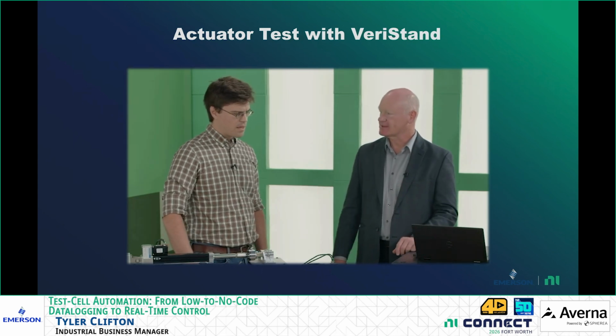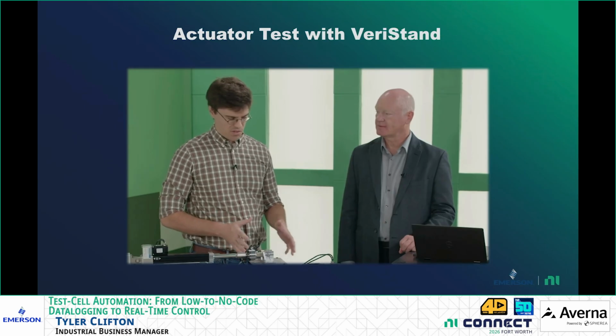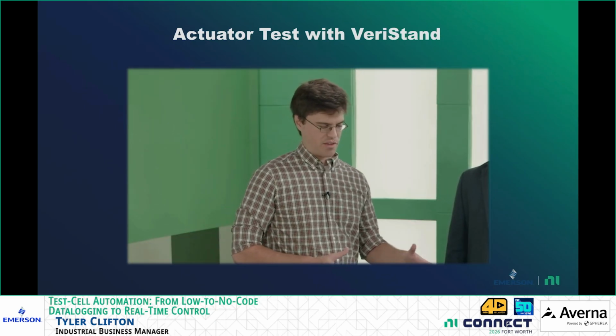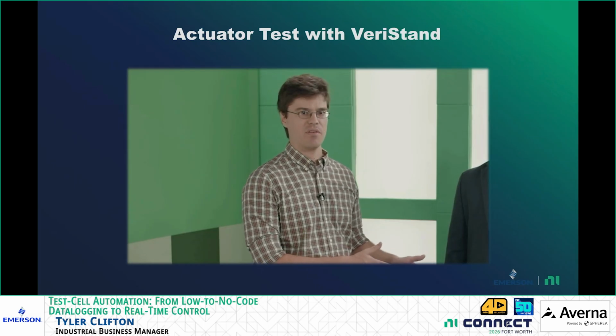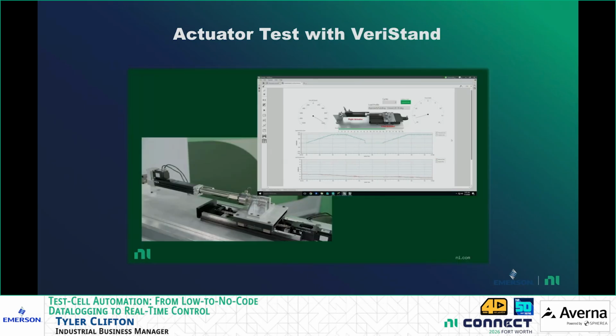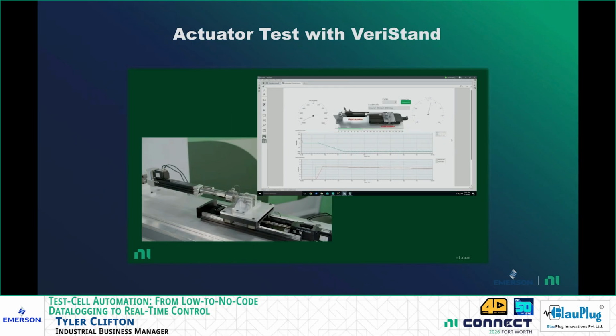So what is VeriStand doing for us? Yeah, so what VeriStand lets us do is it allows us to take that model that is looking at the dynamic load and saying, what should the load be at any point in time? It allows us to run that in a real-time environment and then very easily connect all the model inputs and outputs to physical I/O. All right, and so the model then is developed, so our model was developed in LabVIEW, but we often see models being imported from Simulink or just any C or C++ environment, or really any modeling environment that lets you export an FMU.